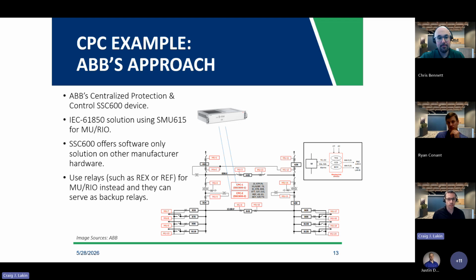And then one of the next benefits that ABB offers, which other vendors as well offer, but I just want to touch on this specific example, is instead of having merging units at each breaker or each transformer, you could have a backup relay out there, such as their REX or REF kind of feeder overcurrent relay. And what that does is it allows you to have the merging unit function, obviously, which will be transposing the signals to a communication base for the centralized protection to perform the actual functions it needs to, but it also can act as backup relays for you.